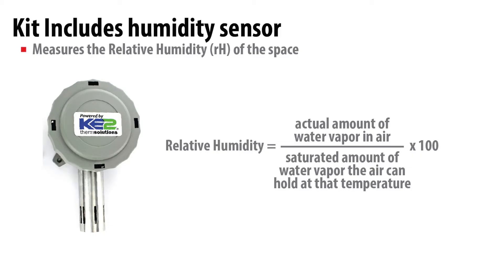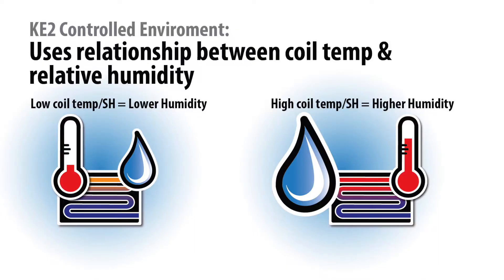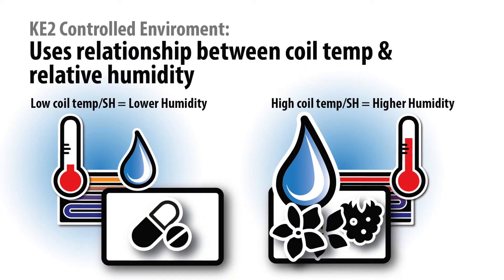The KE2 Controlled Environment kit includes a humidity sensor which measures the relative humidity in the refrigerated environment. The controller will manage humidity in two stages. First, the controller uses the refrigeration system's inherent dehumidification property and maximizes it by increasing and decreasing the coil temperature to remove more or less water depending on whether the humidity needs to be increased or decreased. You can also add an external digital switch for a humidifier, dehumidifier, or external electric heat.